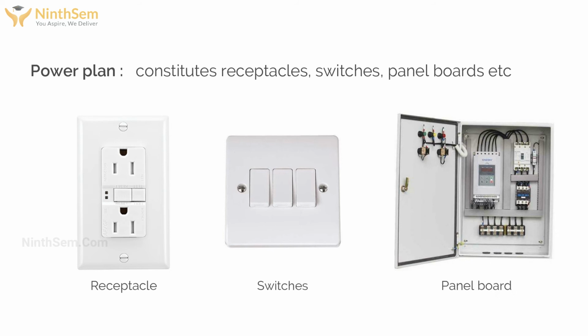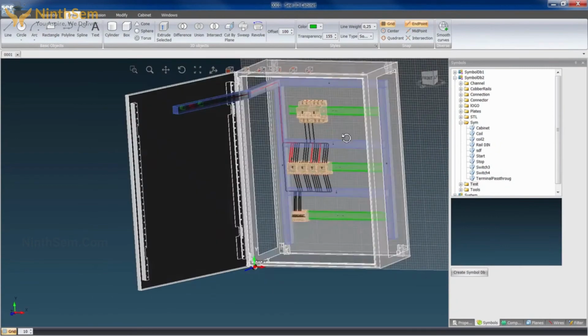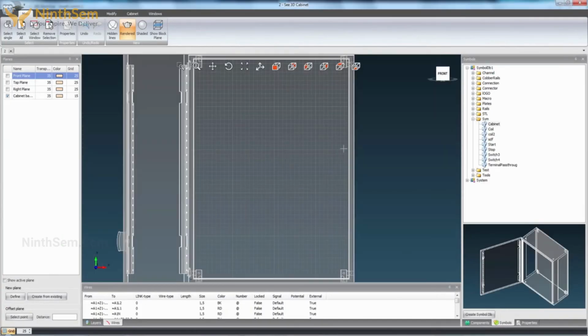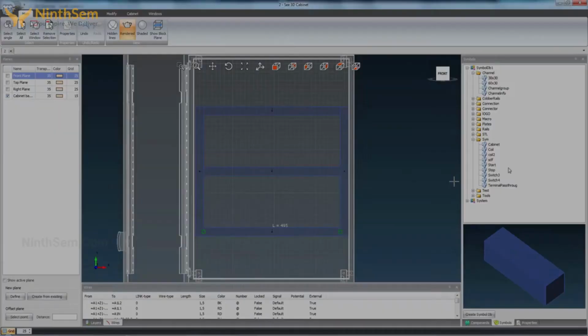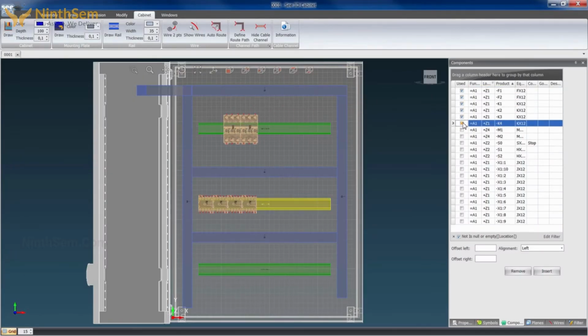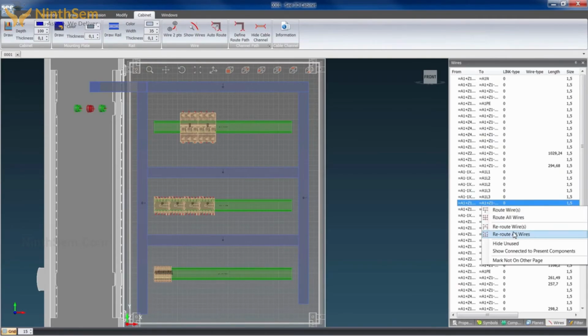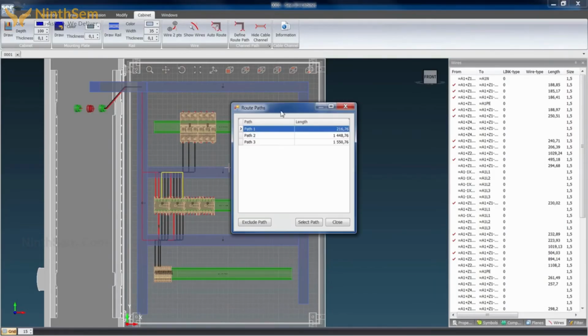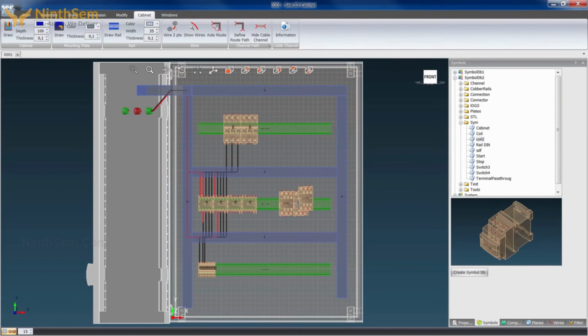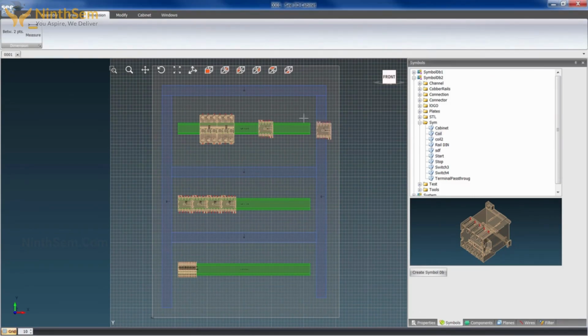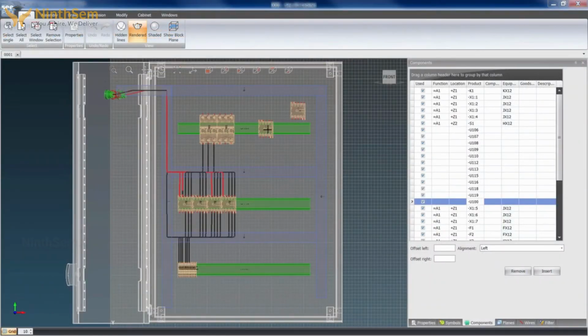Panel boards are the components of any electrical distribution system which divide an electrical power feed into branch circuits, while providing a protective circuit breaker or fuse for each circuit in a common enclosure. A 3D model of each element can be made as per the submittal provided by the client. kVA rating, voltage rating, current rating and dimensions of these elements are some of the key features which should be given utmost importance while preparing the 3D model of these elements. Once models of these devices and equipment are prepared, they are also placed in the architectural layout for coordination.